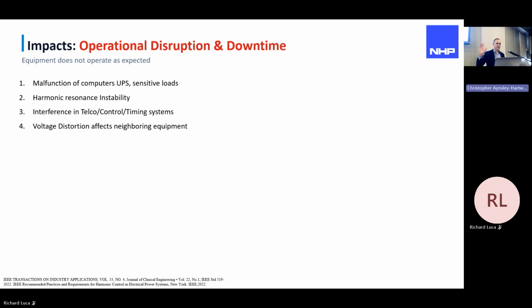another site I attended, a commercial property, the client was experiencing a lot of appliances blowing. We couldn't exactly figure out what was going on, but we knew that it was being fed by a few hundred meters down to a shared transformer. It was being shared by a few different businesses, and one of those businesses was a large sawmill. And in the afternoons, they'd start up a big bandsaw. And we found that, okay, there's a lot of transients flowing through the network, distortion coming and affecting this business. So he went back to the utility and requested some more investigations.